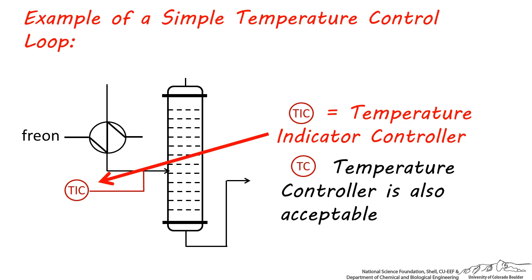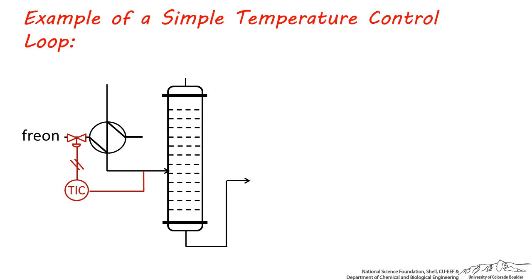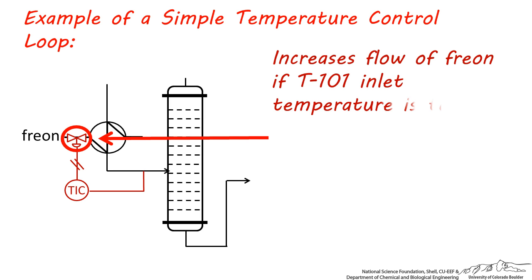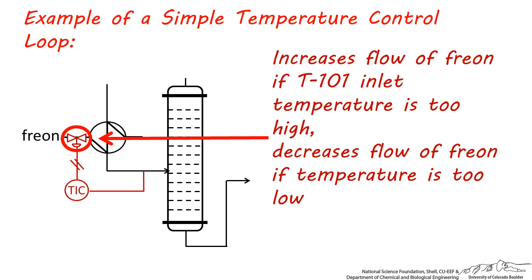If it's too high or too low, the controller will send a signal, which will open or close a control valve slightly. Let's talk for a moment about this valve and what it's doing. This control valve's job is to increase the flow of freon if the distillation column inlet temperature is too high, and decrease the freon flow rate if it's too low.